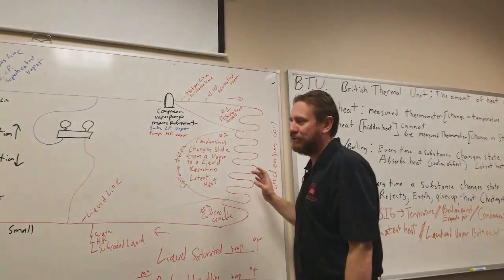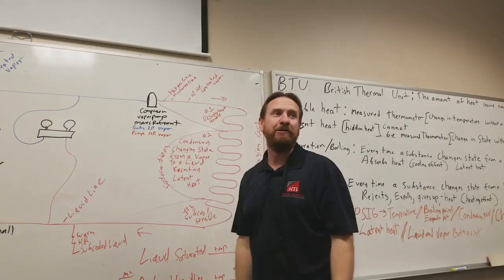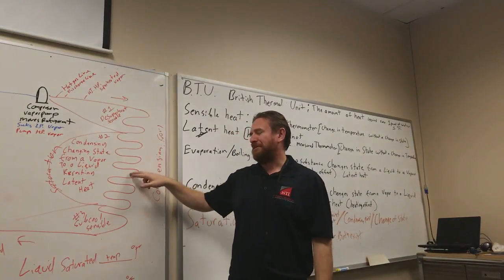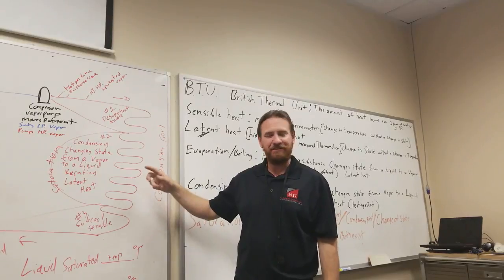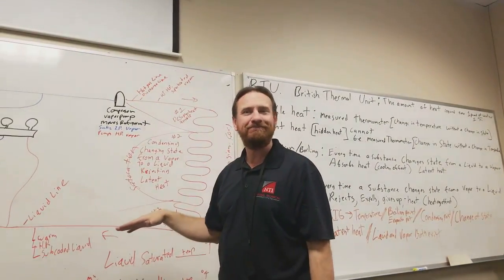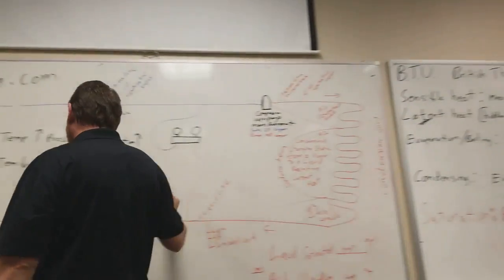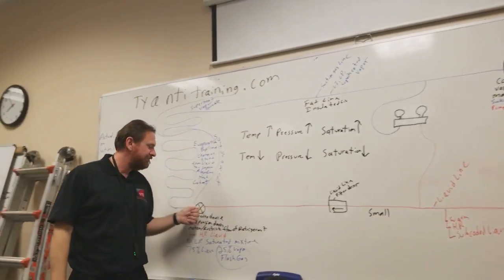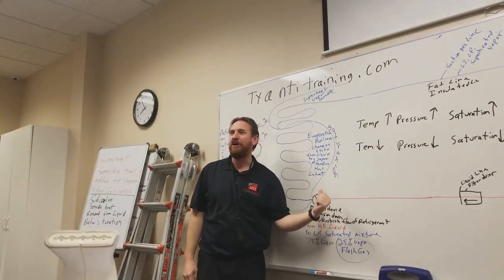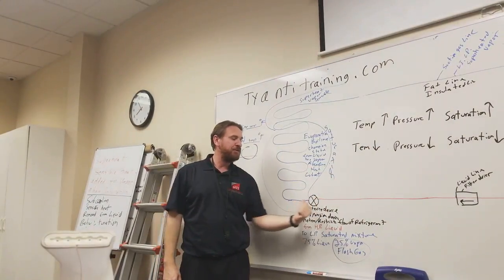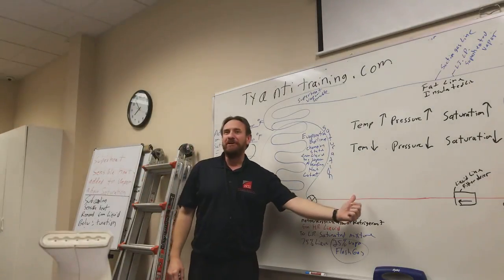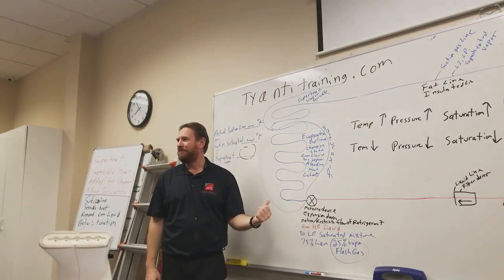Now here's the catch, the inside pressure has a few variables going on. As my outdoor temperature goes up, what's happening to my outdoor pressure? It's going up. Now there's pressure pushing against that liquid, right? Now if there's more pressure pushing against the liquid, and this is just a fixed hole, and there's more pressure pushing that liquid harder, what's going to happen with the refrigerant coming to the hole? More liquid. More liquid will be pushed through the hole.